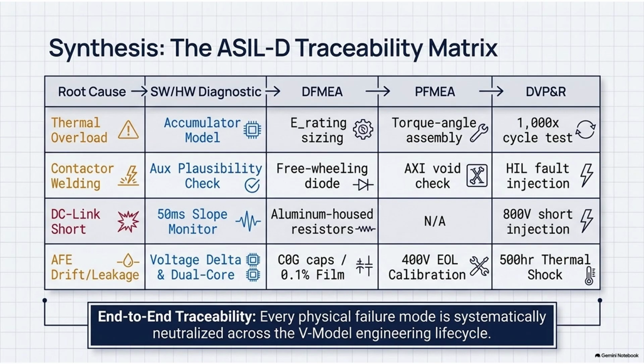And they subject the unit to this combined shaking, freezing, and boiling ordeal for 500 solid hours over 20 days straight while the unit is powered up and functioning. And the acceptance criteria for the electrical signals during those 20 days is absolute zero tolerance. Throughout the entire 500-hour ordeal, sophisticated monitoring equipment tracks the microcontroller signals steering the high-voltage relays.